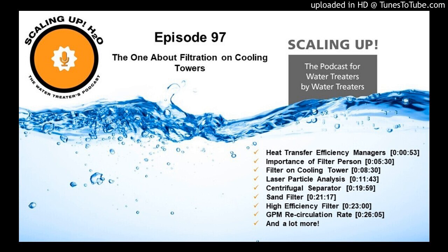So backwashing should be done a minimum of every 24 hours to be sure you don't get biogrowth in the filter tank. And then the real control on backwash is whenever the pressure differential gets up to a limiting point, the filter automatically goes into backwash. So generally, the 24-hour backwash timer doesn't even get used, but it needs to be there in case something isn't going right. It's got to be backwashed every 24 hours. Now, you mentioned media fouling. So we have regular backwash that's cleaning the media, but now eventually the media gets worn out. We've got to replace it. What is that process like, and how often should we be doing that?